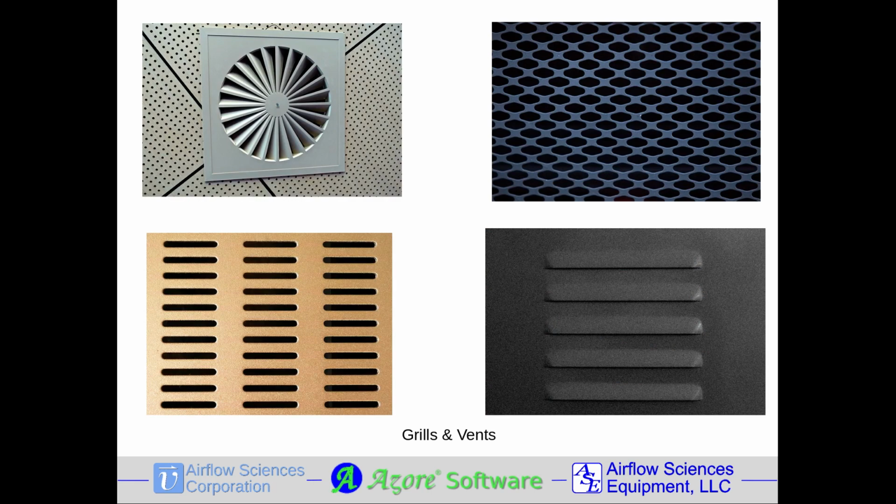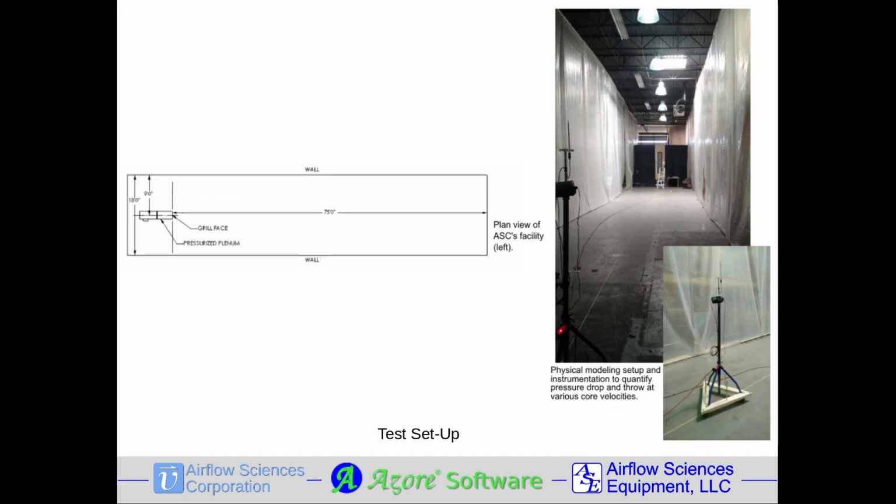It is used to define laboratory methods to test ducted and unducted systems for distribution and return of building air. It includes specifications for test instruments, facilities, installations, and procedures and methods of calculation for determining aerodynamic performance. Typical air inlets and outlets consist of grilles, registers, diffusers, vents, and slots.